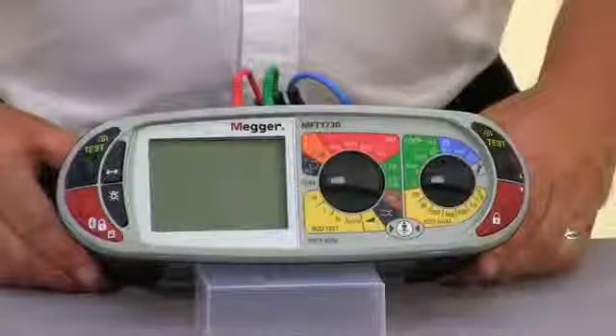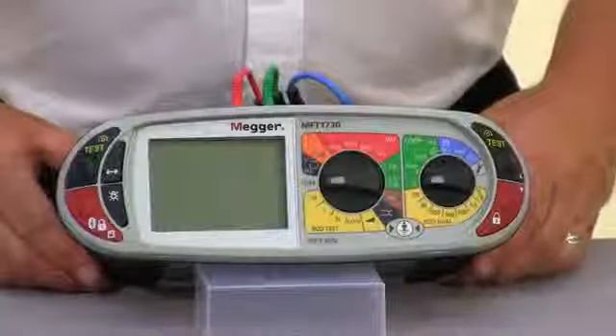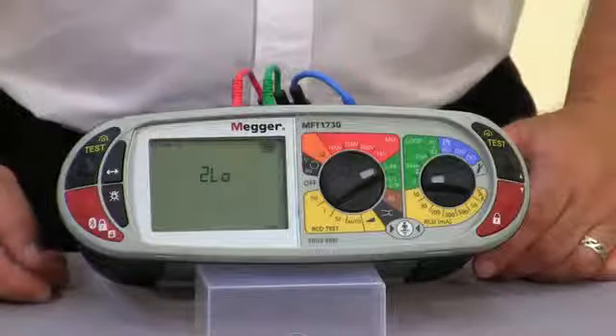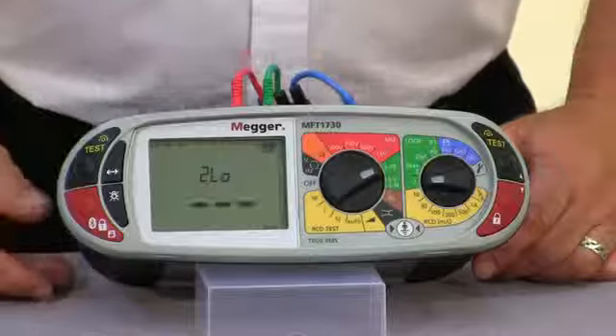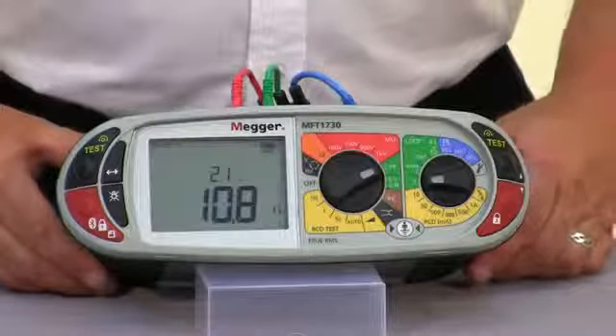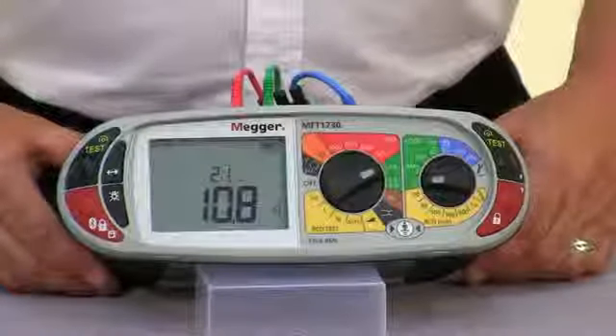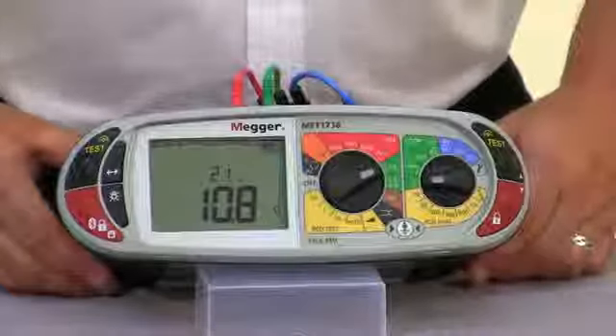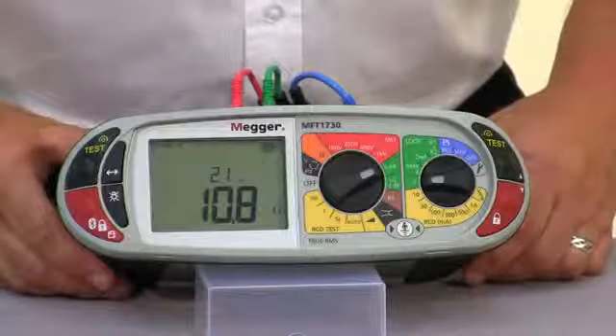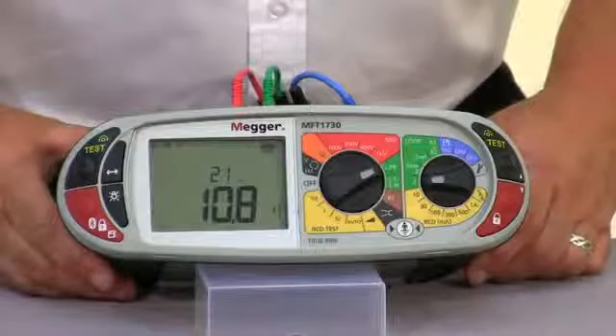So now we'll run through a standard 2-wire no trip test. So you'll see now that we only have the live and the neutral connection, and we go to our LPE setting, and on the screen obviously we have to cycle through from our default, which is our 3-wire, to select 2 high and then down to our 2 low. Again, apply the mains voltage, and the unit, once it's seen the voltage there, audibly indicates that it will automatically start the test. Now the 2-wire no trip test is advantageous if you're looking to take a reading on a luminaire circuit, for example, where there's no neutral. So this gives you the facility to actually carry out the test from the light switch. And again, the reading displayed is 10.8 ohms and PFC value on the second parameter at 21 amps.